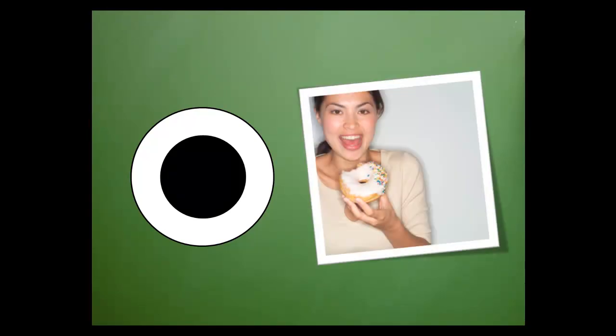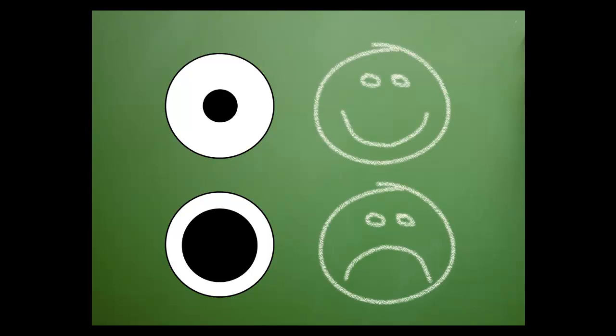Ideally, when I look at the chart I'd like to see a circle with a black dot in the middle. Thinking of this shape as a donut is a good memory aid. Donuts make people happy and seeing this on your chart will make you happy. This tells me that we're not just keeping up with the Joneses, but I'm doing better. My relative CV is less than that of my comparison group. The size of the inner circle relative to the outer one also provides information. The smaller the inner circle, the better our lab is doing. By analogy, I'm better off with more donut and less hole.